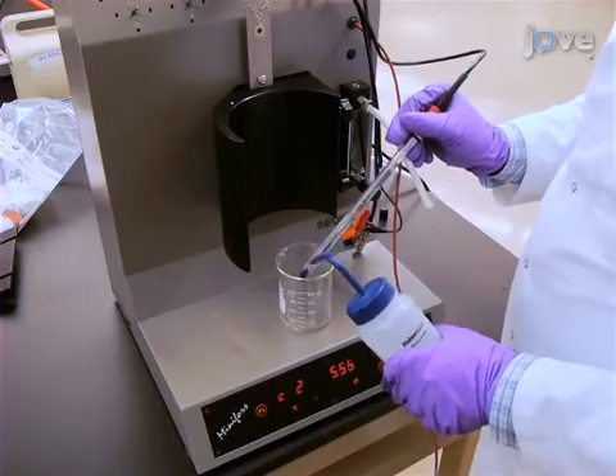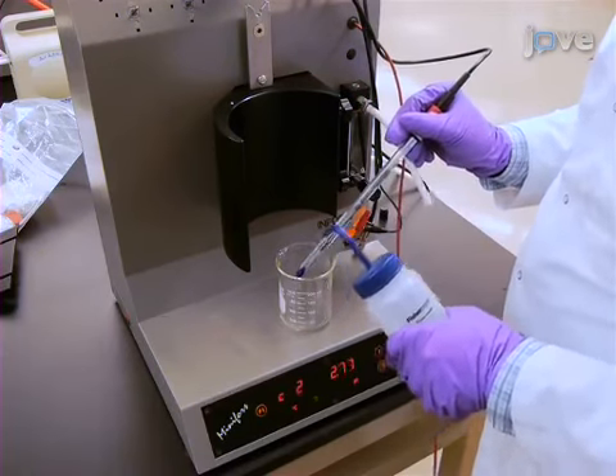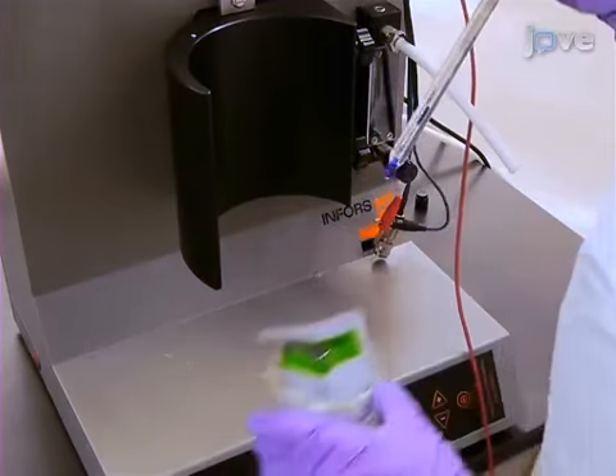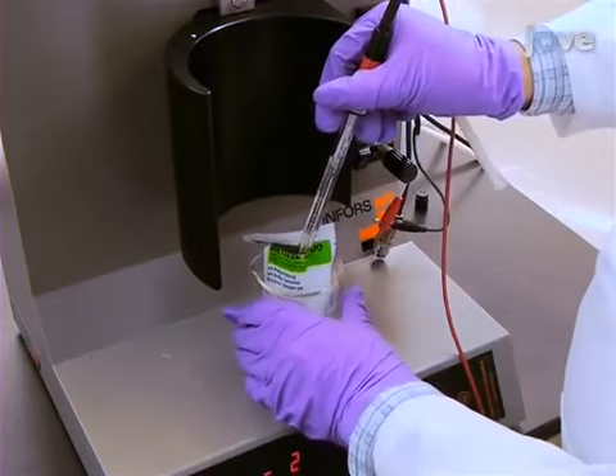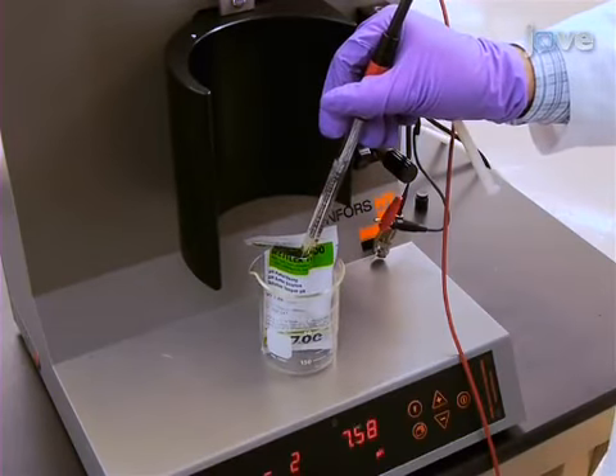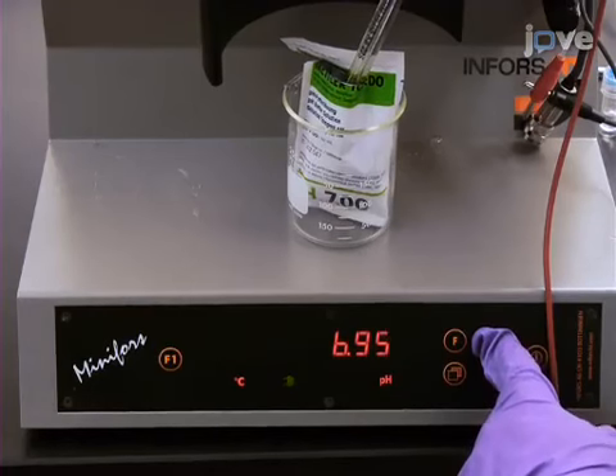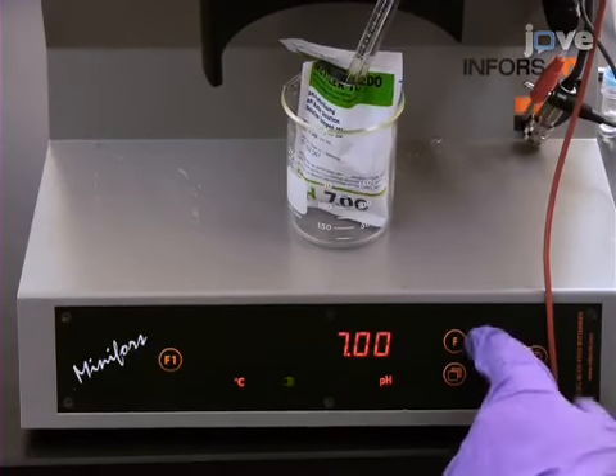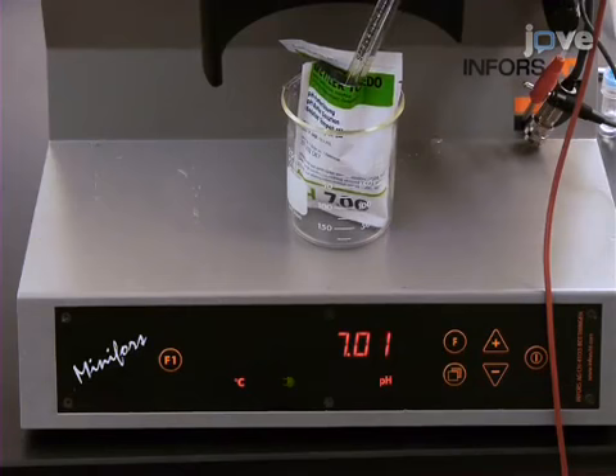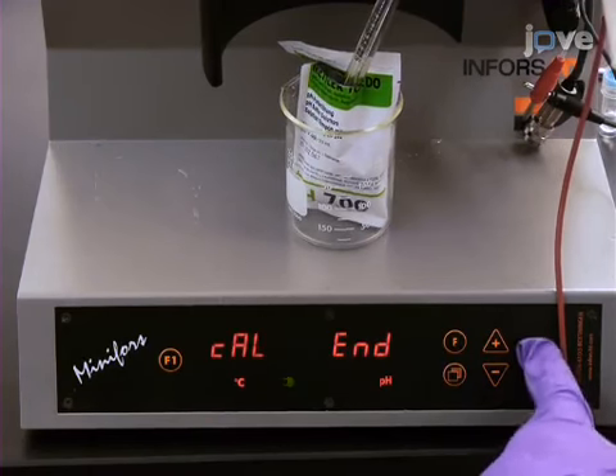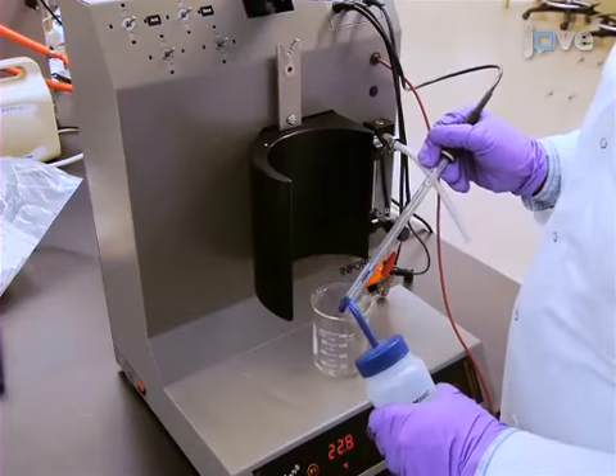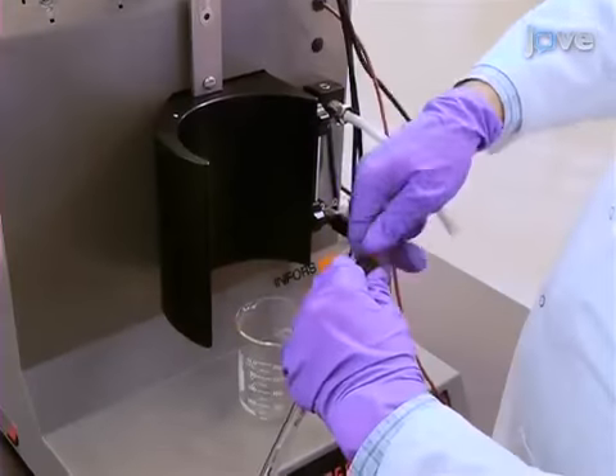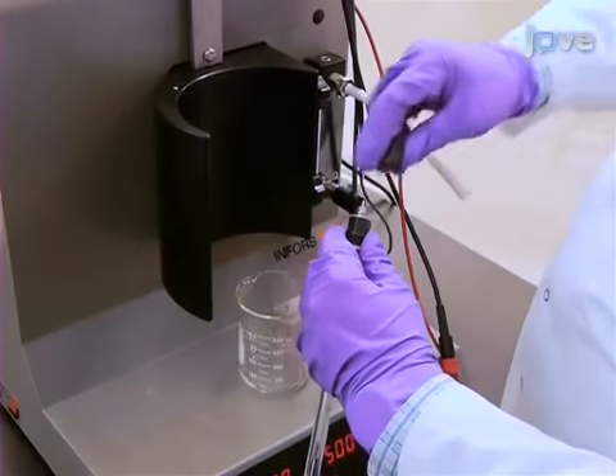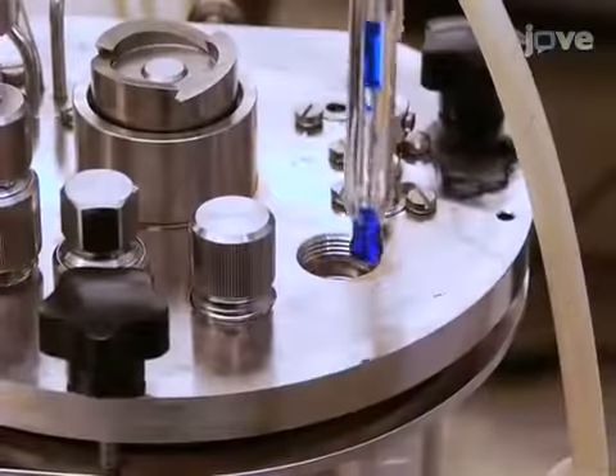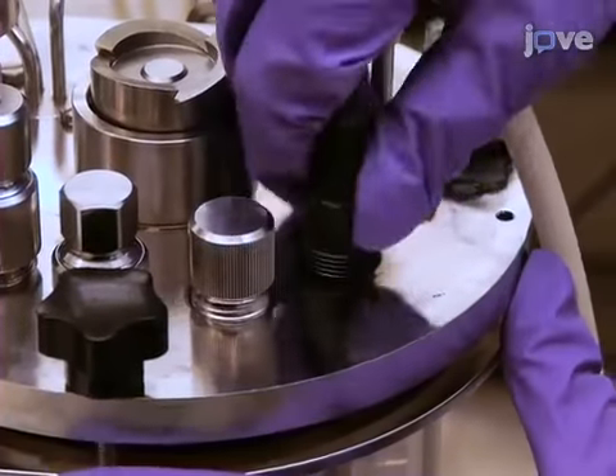Next, wash the low reference buffer off the probe and insert the probe into the second reference buffer. Allow the value to stabilize, and then use the keypad to make the displayed value match the high reference buffer value. Press Enter to confirm. Wash the probe tip and disconnect it from the fermenter. Put the protective cap on the connection and install it in the head plate.